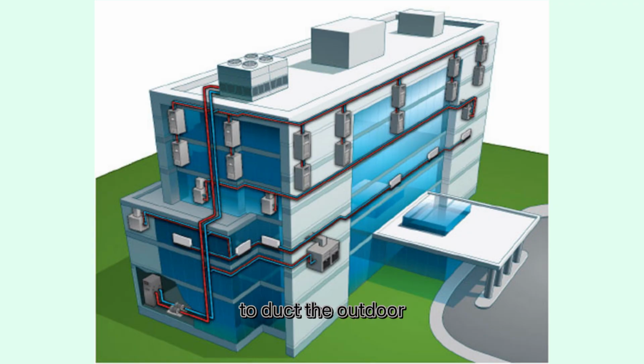The second method is to duct the outdoor air to the WSHP return plenum. Here, the outdoor air mixes with the return air before passing through the WSHP coil. This allows the incoming air to be properly filtered, cooled, or heated, ensuring consistent comfort across the zone. However, this method requires the fan to run continuously during occupied hours to maintain airflow and proper ventilation. In most commercial WSHP systems, this second method is the recommended and more effective approach for introducing outdoor air.